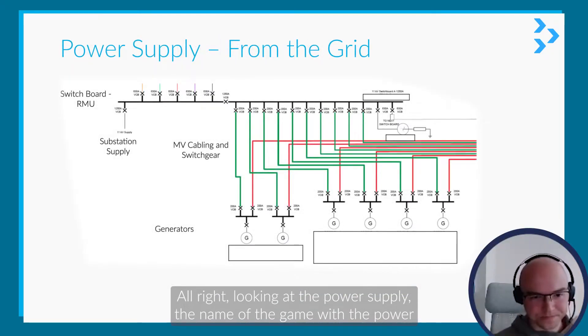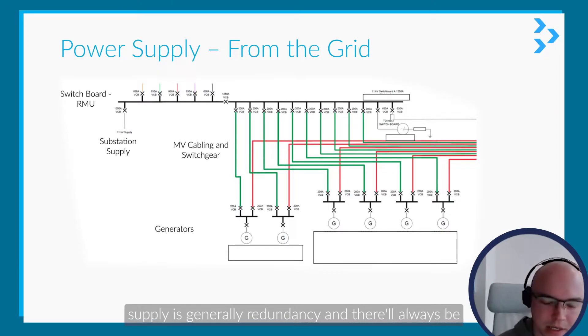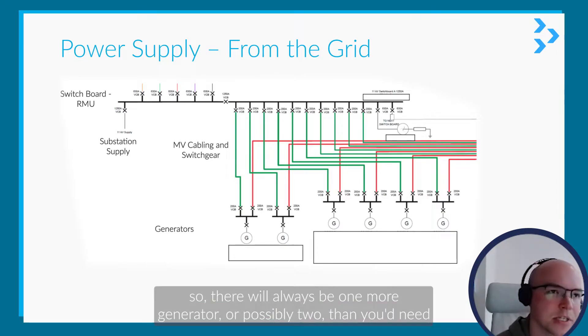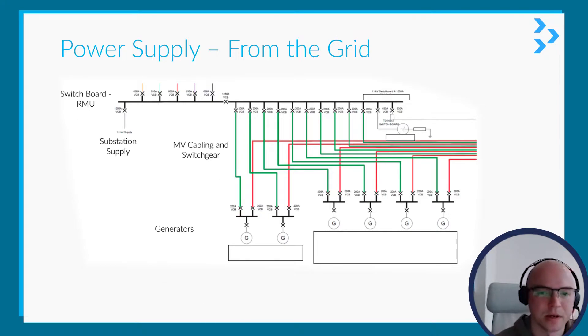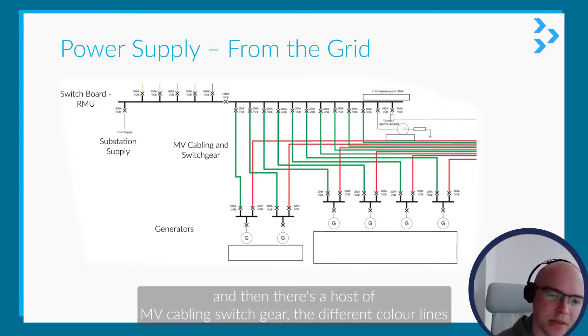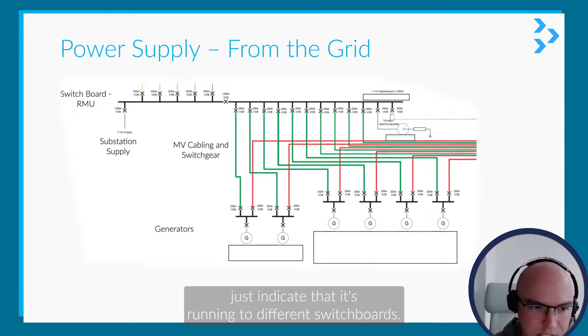Looking at the power supply, the name of the game is generally redundancy. There'll always be generators and they operate on an N+1 philosophy, so there'll always be one more generator — possibly two — than you'd need to run the equipment. How it's set up on this drawing, there are generators at the bottom and then a host of MV cabling switchgear, with different color lines indicating runs to different switchboards.